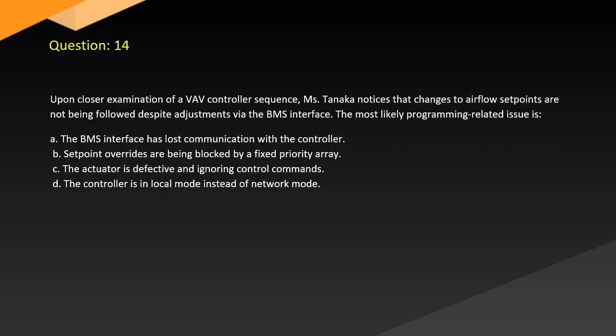Question 14. Upon closer examination of VAV controller sequences, Tanaka notices that changes to airflow set points are not being followed despite adjustments via the BMS interface. The most likely programming-related issue is: A. The BMS interface has lost communication with the controller. B. Set point overrides are being blocked by a fixed priority array. C. The actuator is defective and ignoring control commands. D. The controller is in local mode instead of network mode.